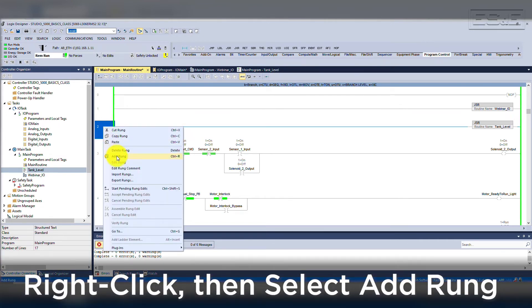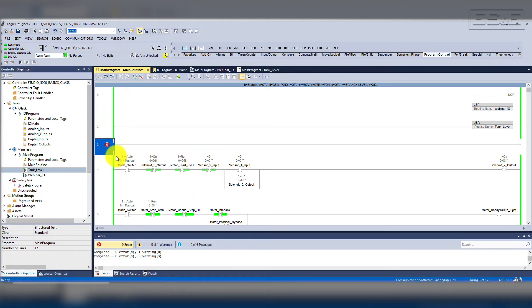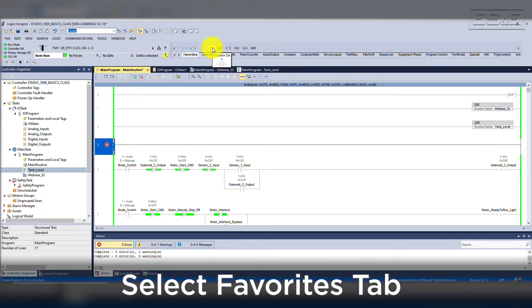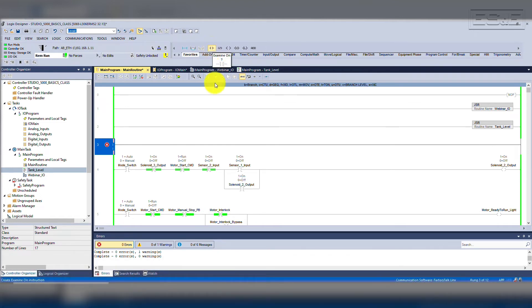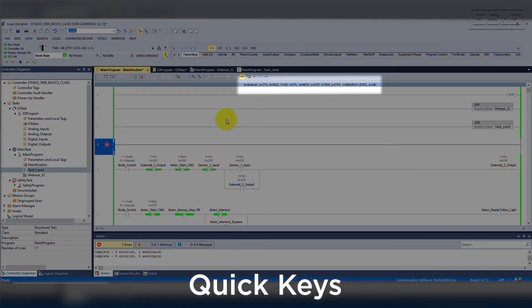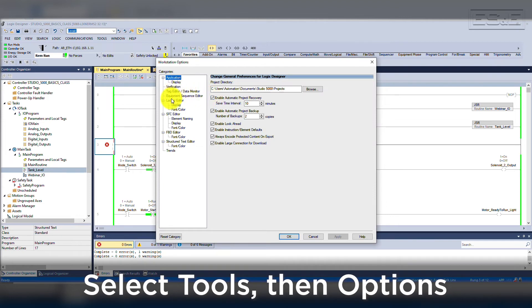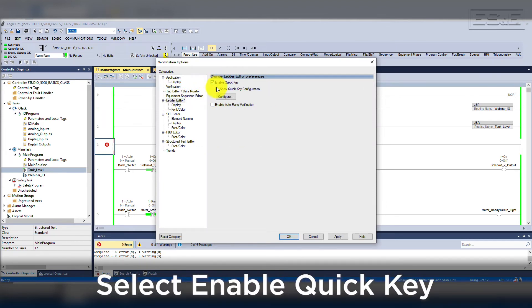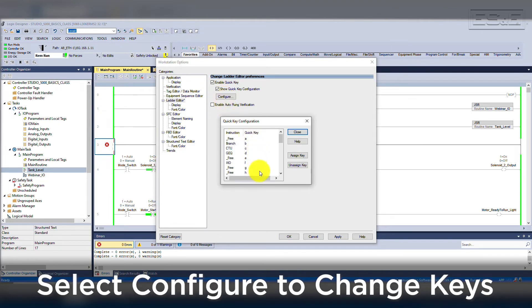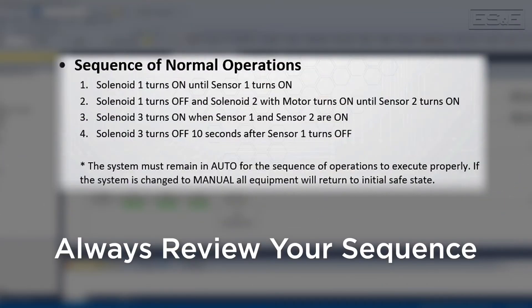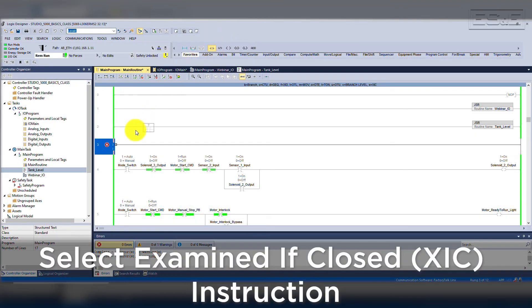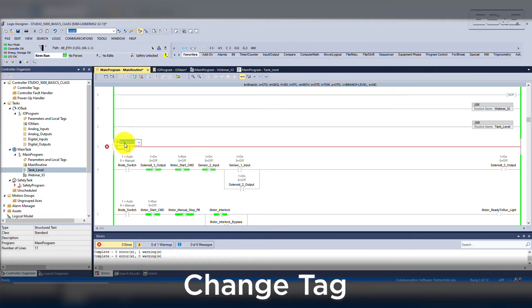Returning to the main routine, we will add a rung for the missing logic needed for our Solenoid 1 output. We will right-click on Rung 2 and select Add Rung, which will start a new rung that we can edit while online. Then we will select our Favorites tab in the Instructions toolbar, which shows the most common ladder editor instructions. I also have Quick Keys enabled, which can be seen at the top of the main routine tab. Quick Keys can be enabled by selecting Tools, Options, Ladder Editor, and then selecting the checkbox to enable Quick Key. You can change the Quick Keys by selecting the Configure button if you do not like the default configuration.